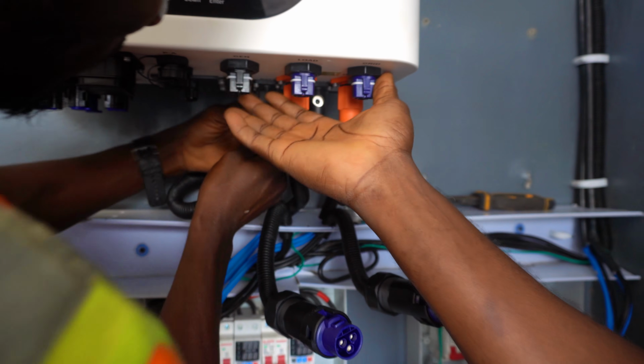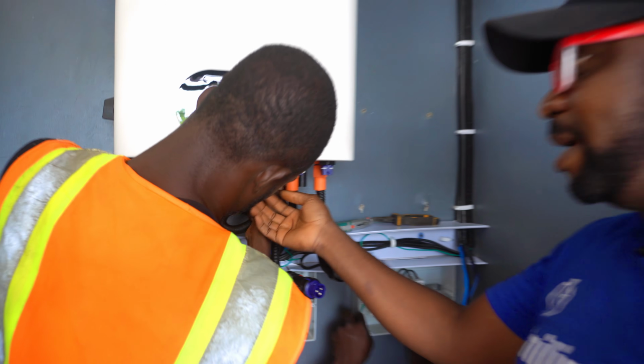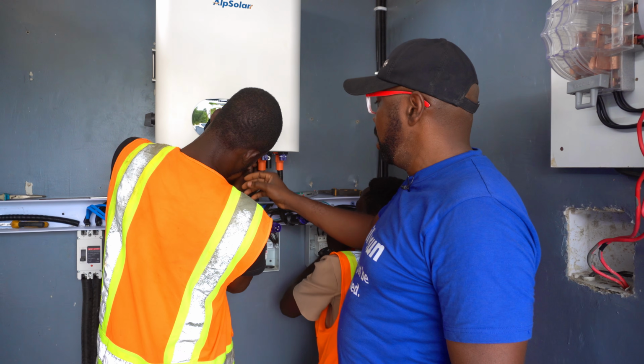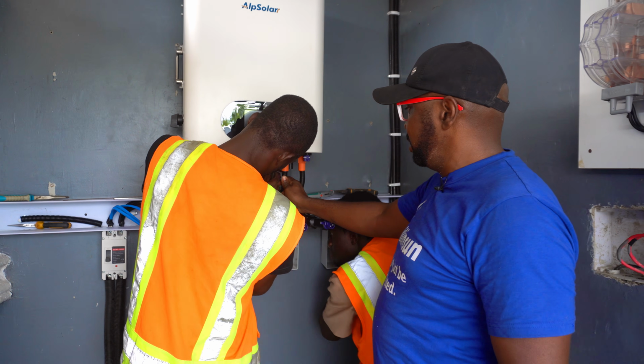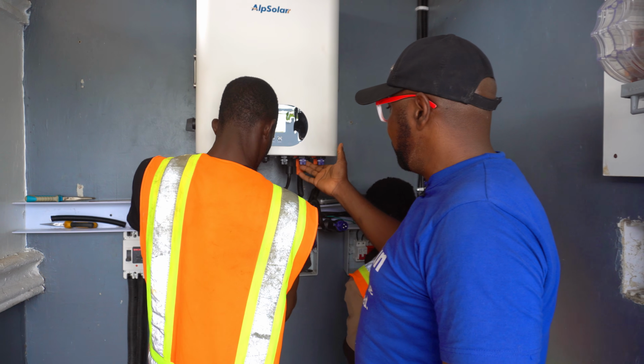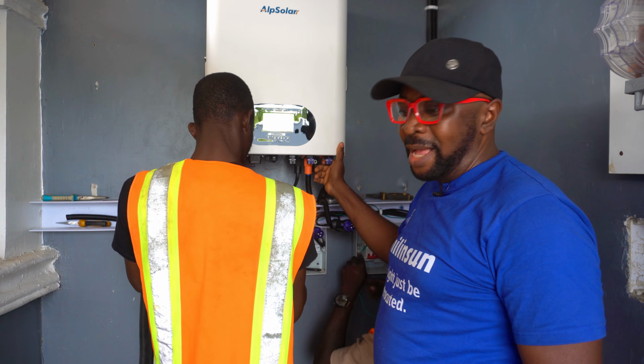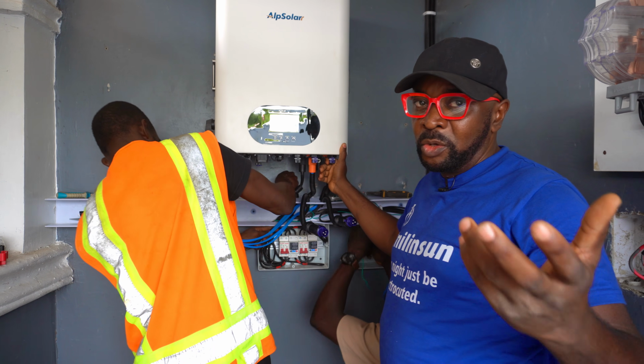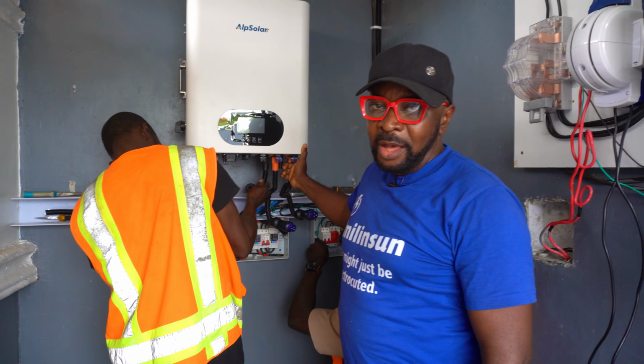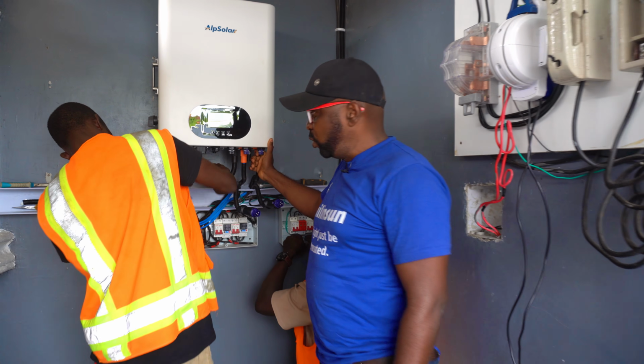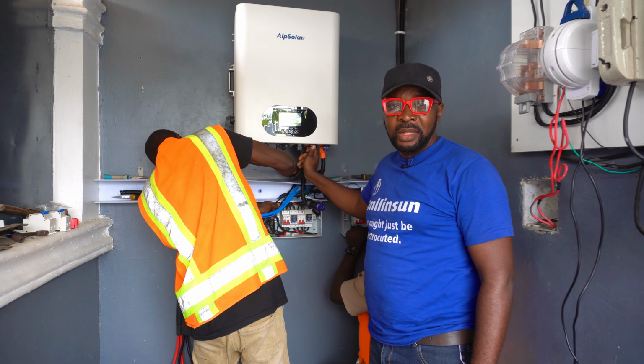We don't have any of those automatic gens that we're meant to connect here, so we're going to let the gen port be, but the load port is going to be connected down here. Each battery terminal here would have to be assigned to each of the batteries. We have a 200 amp hour battery here, a C-watt battery, so each of them is going to be assigned to one of the terminals.